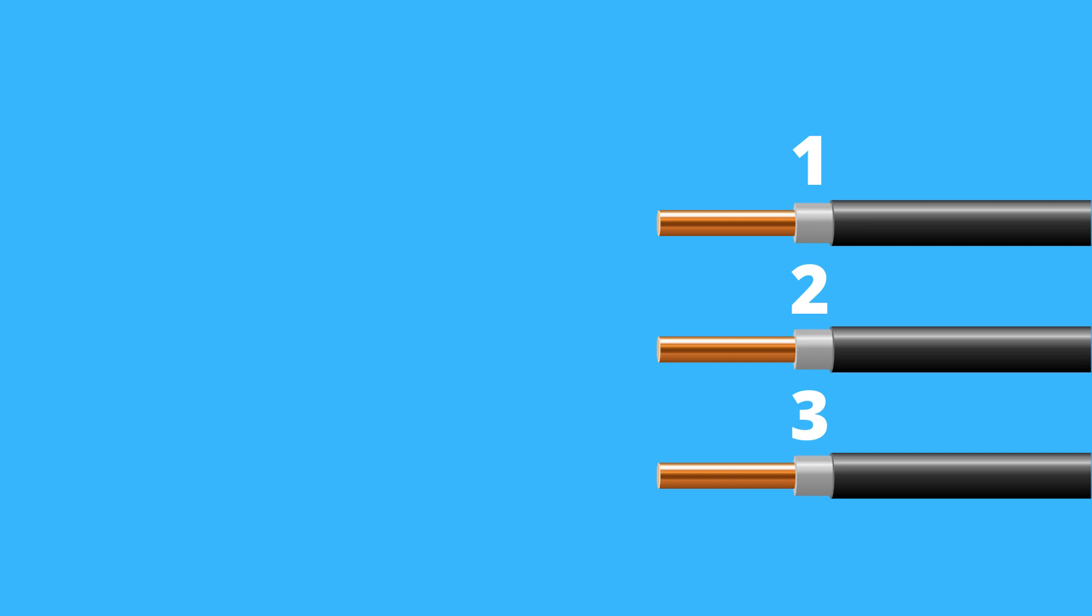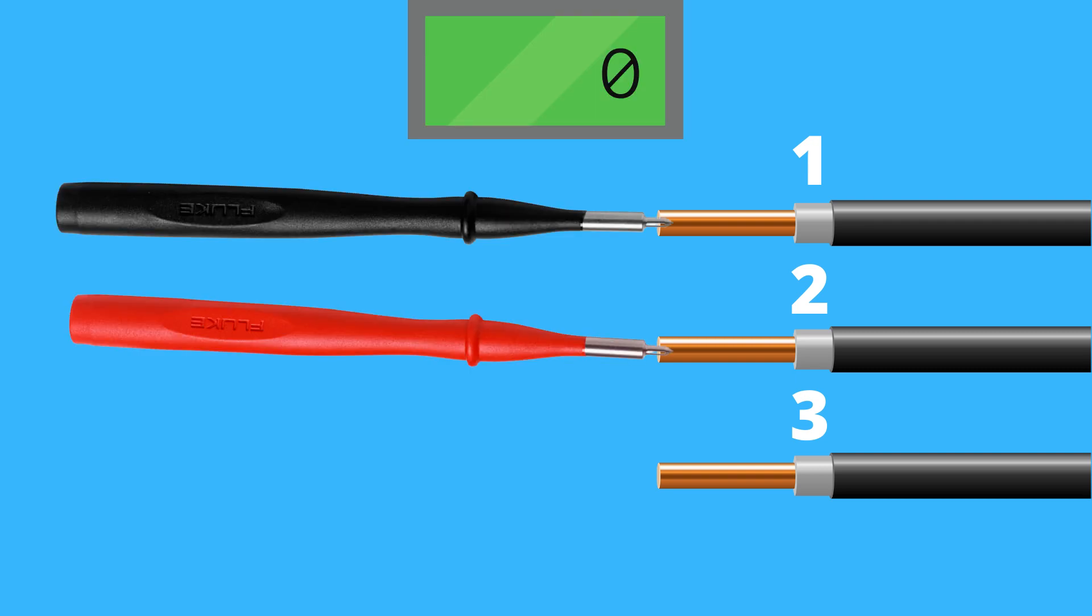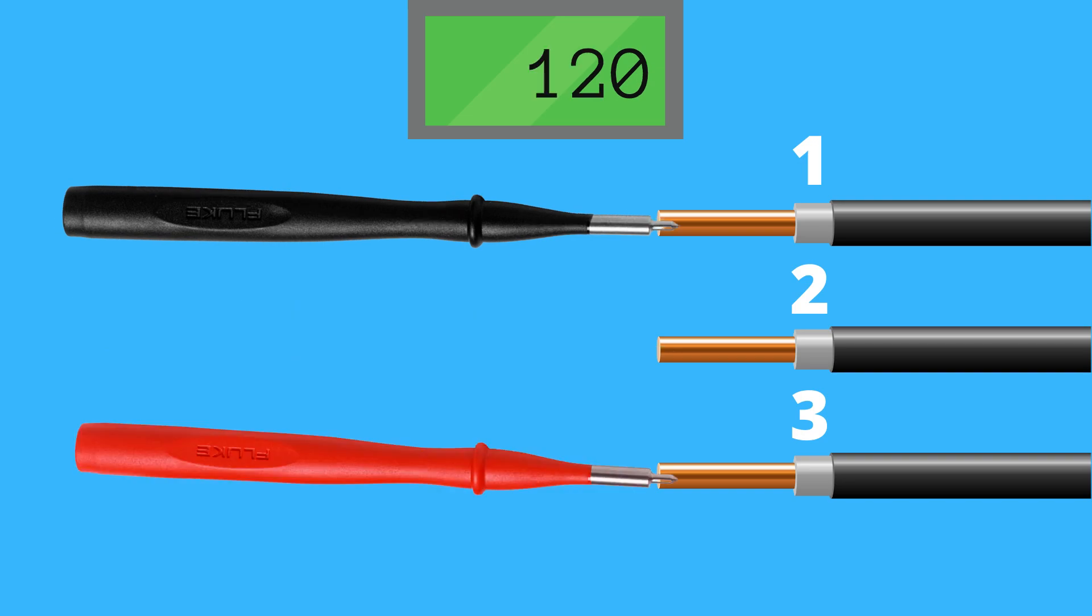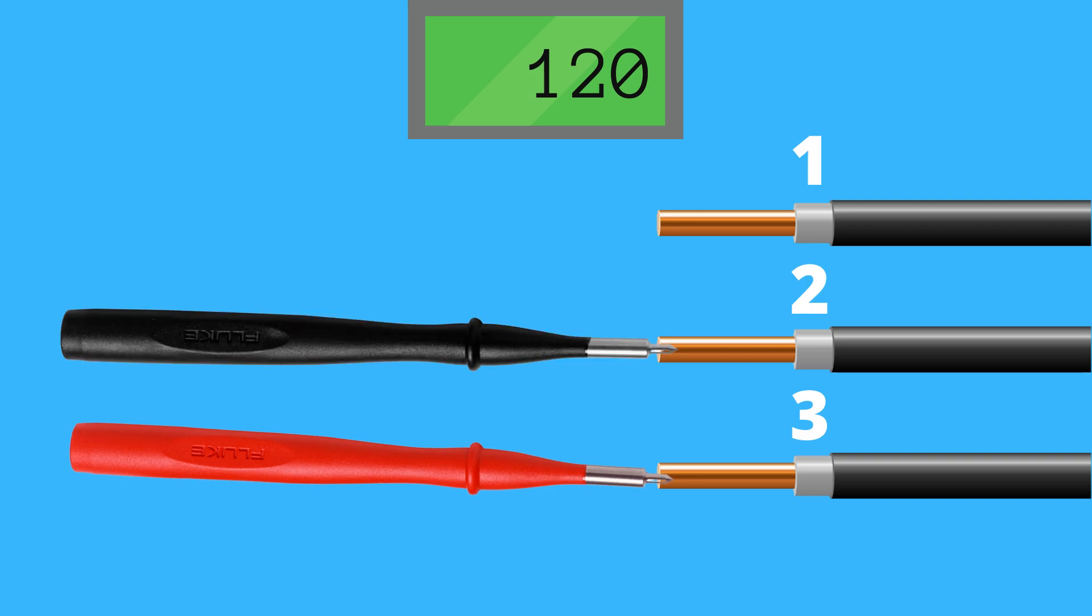Mark the wires with numbers or colors. Then measure the voltage on the first two wires. If you get a result of zero volts, you found a neutral and ground wire. Now move on to measuring the third wire. If you get a result of 120 volts or 240 volts if you live in Europe, you found a hot wire.